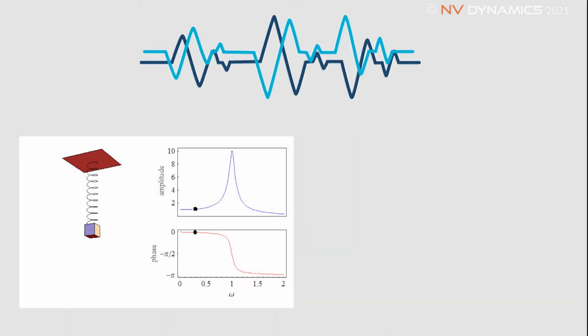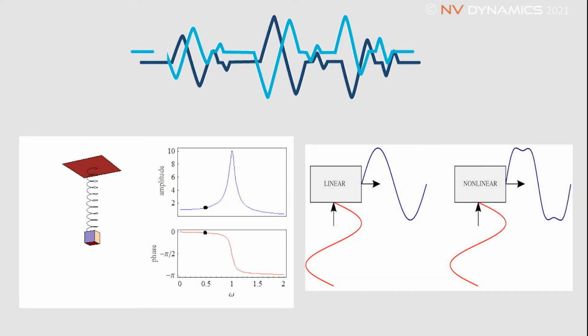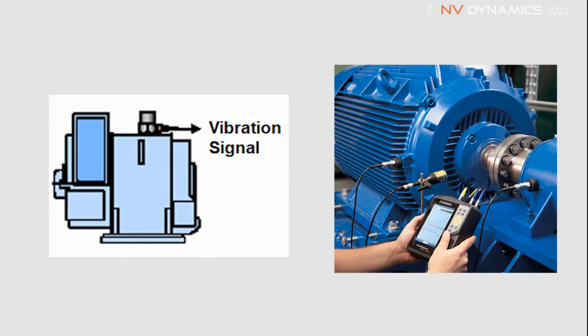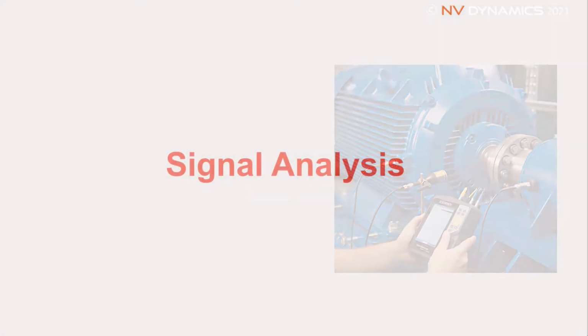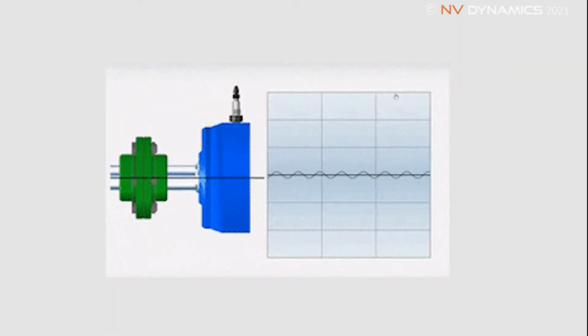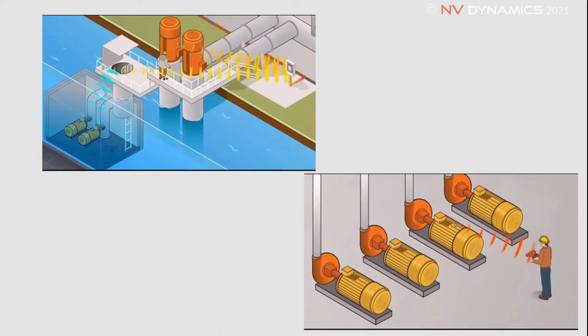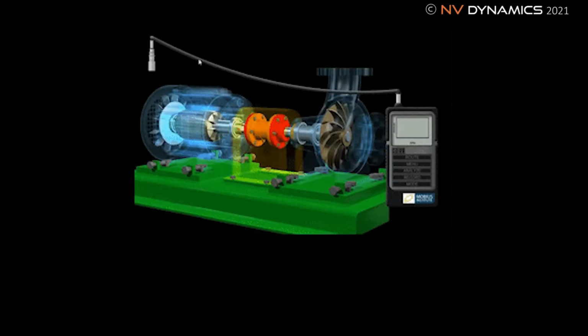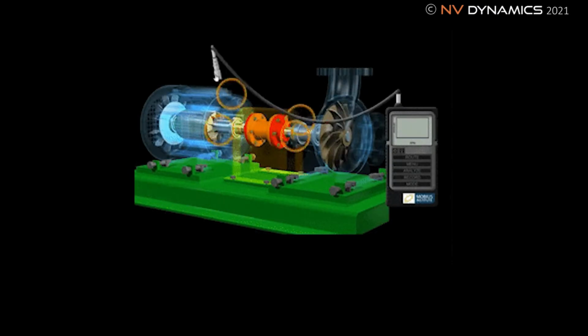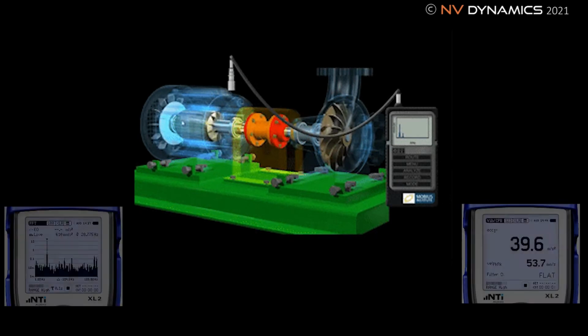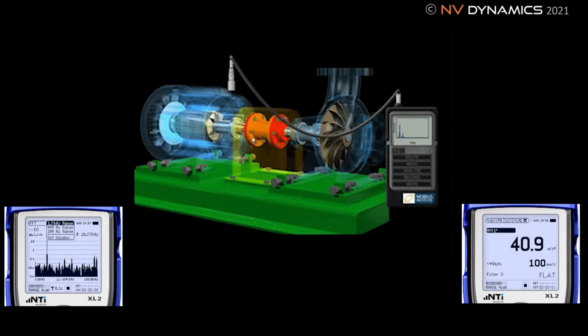Vibration as a physical parameter is a significant indicator of dynamic response and health of any mechanical system, both linear and non-linear. Most linear responses are assessed and analyzed using output only data, which is also called signal analysis. This involves a good amount of understanding of the equipment under test, its kinematics and operational details, loads and overall system configuration. This approach is mostly used in either machine health assessments like condition monitoring or in root cause analysis and investigative tasks.